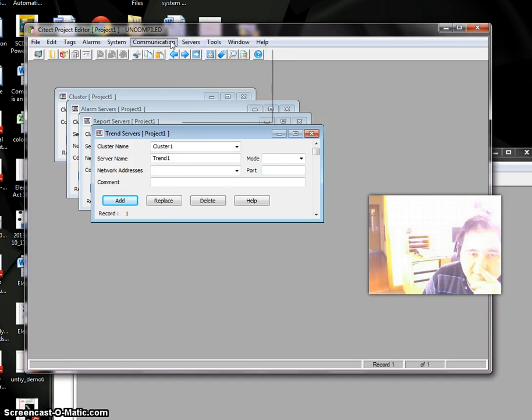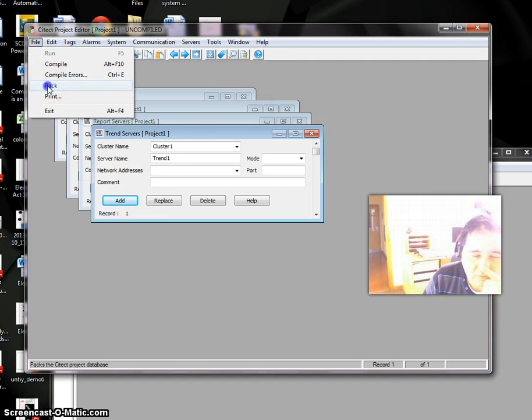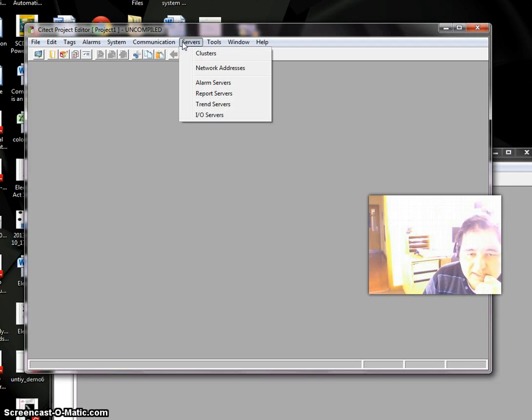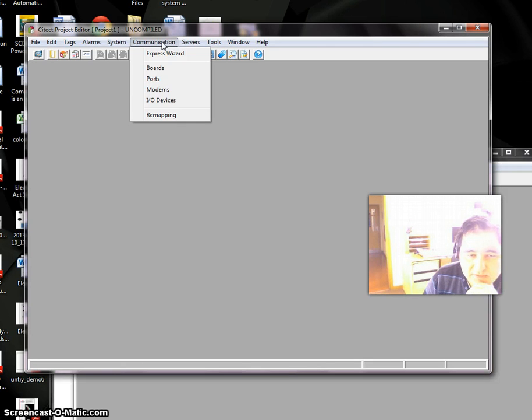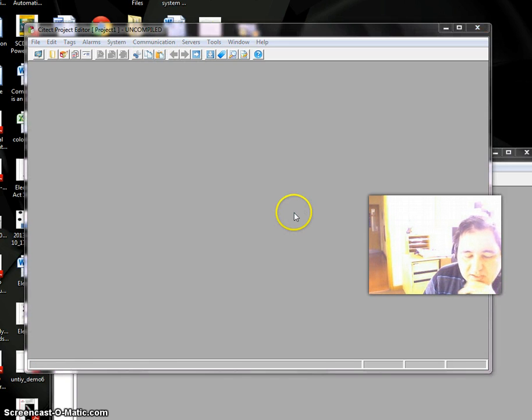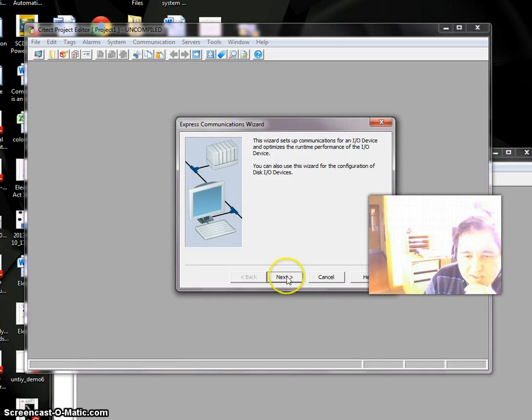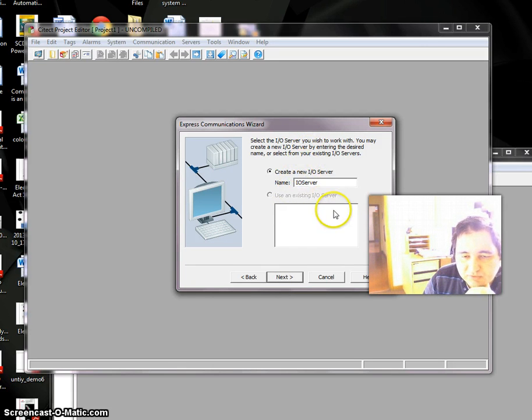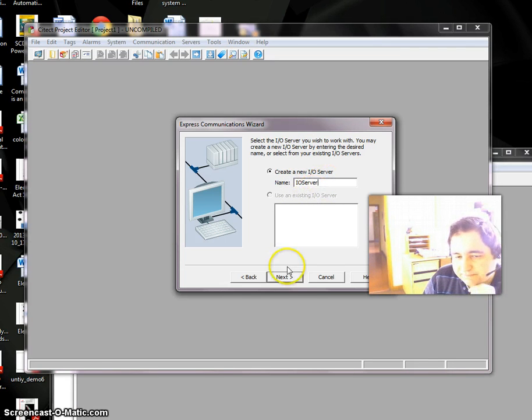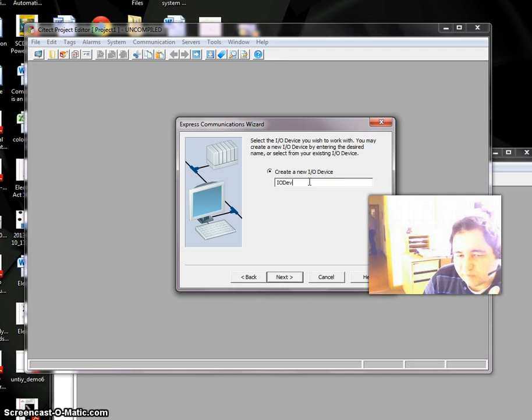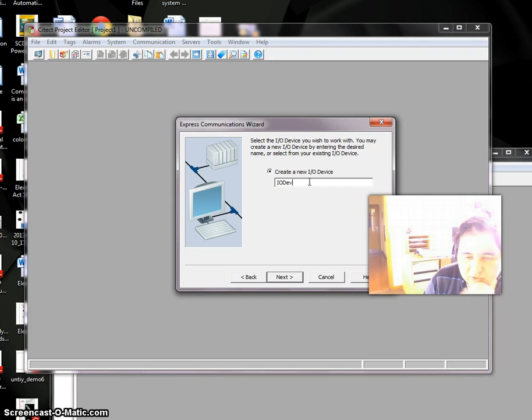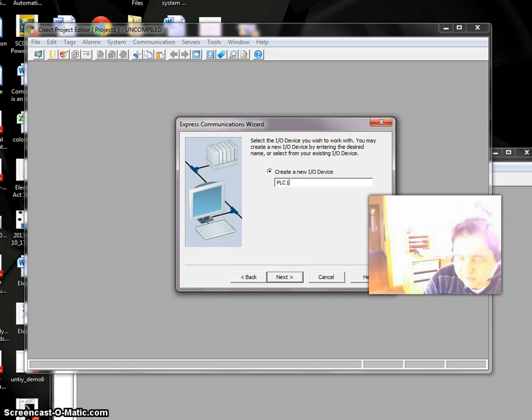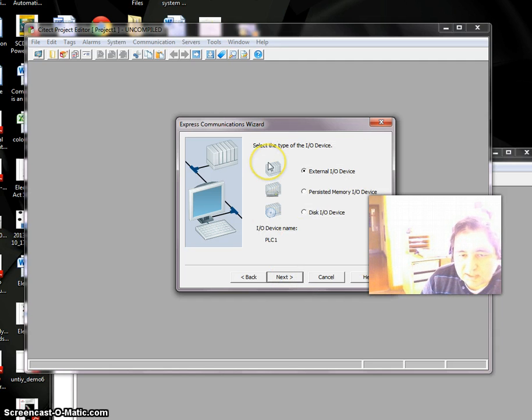Now I have these servers, so I can Pack my file. The next stage is Communication. Go to Communication menu and Express Wizard. Click Next. It says you don't have any IO Server—do you want to make one? By default the name is IO Server. Then IO Device—we may have multiple IO devices, but you need at least one. By default it's IODev, but let's call it PLC1. Next.